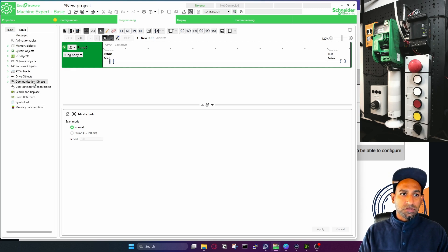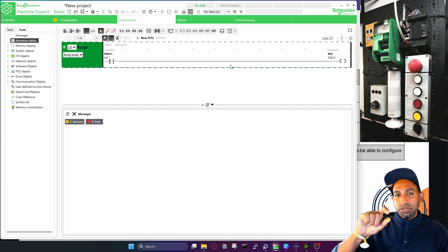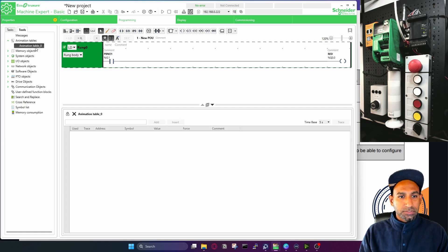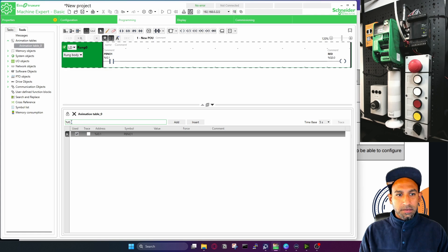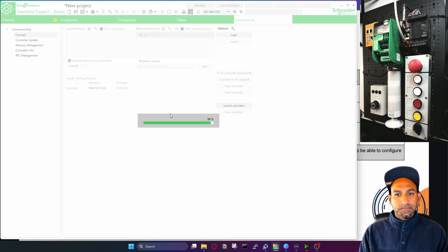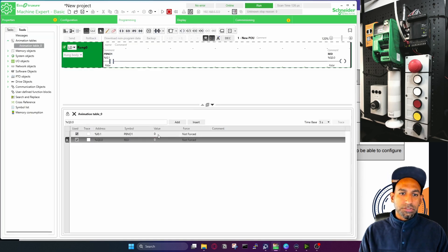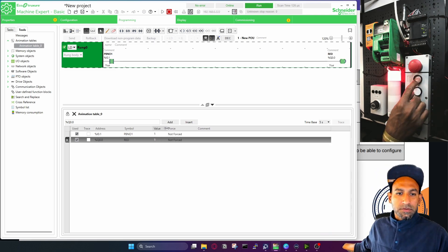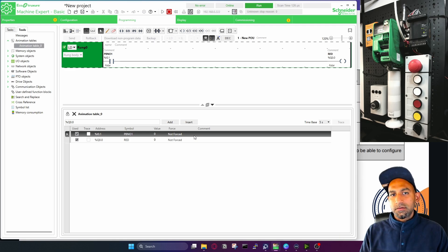Now if you come to the tools tab, in messages you can find any warnings or errors. The animation table is a watch table — if you want to monitor specific inputs and outputs, click animation table, create a new table, and type the address (e.g., i0.1, q0.0). With the controller logged in, you can see those values being monitored in real time. Actuating i0.1 shows it's 1 and the output is 1 as well. You can also trace values here, which we'll use more with analog inputs.